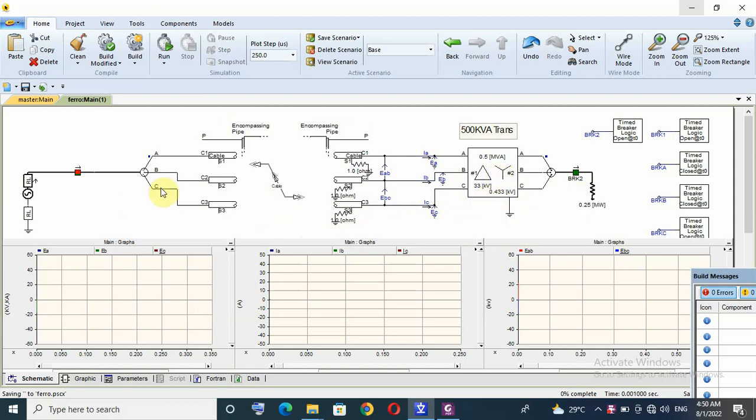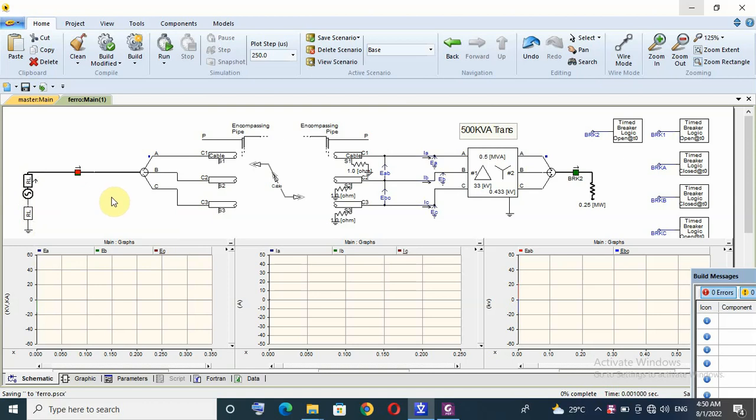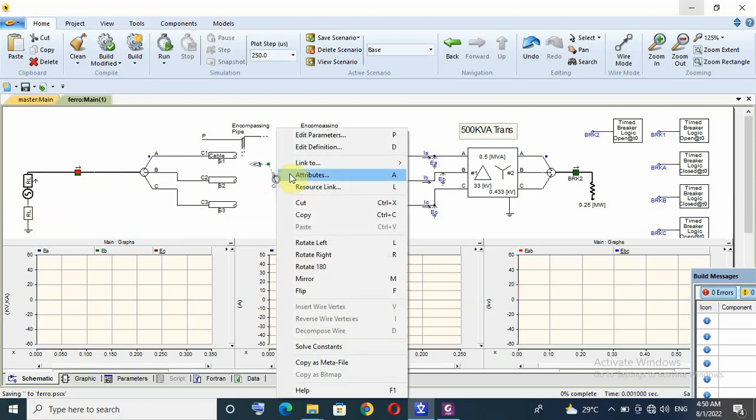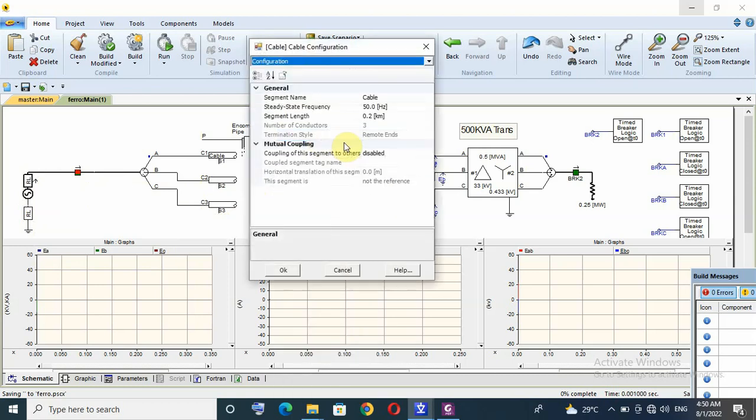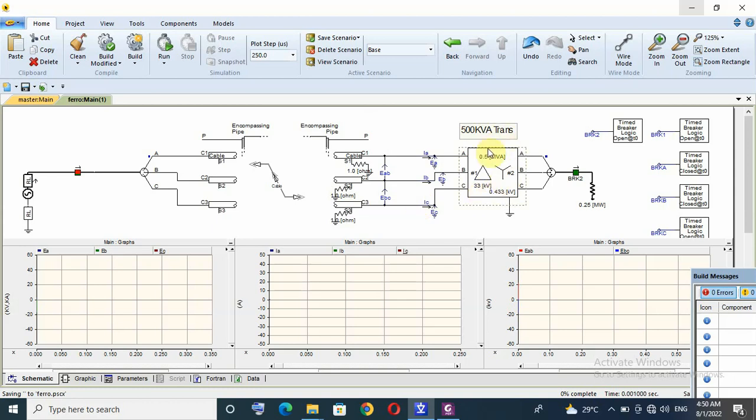So, our configuration, we have supply 33 kV, then we have fuses, long cable about 200 meter, 185 millimeter square. Finally, we have transformer, 500 kVA transformer with no load at secondary side.